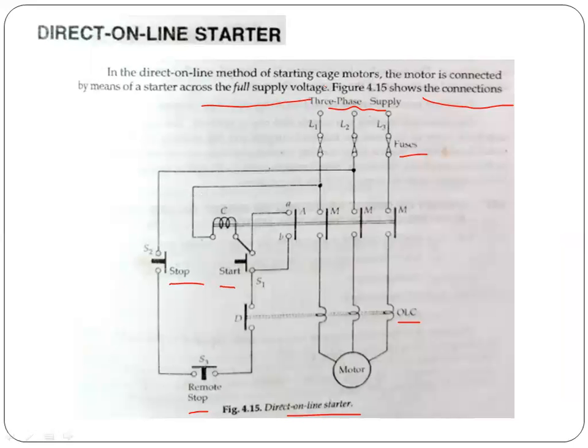So, see, this is the C point. This is the contactor C. Now this contactor is connected with the lines of the supply. When this start push button is pushed, then this contact gets closed and this coil gets energized. This will attract this auxiliary switch and these main contacts, and this path will be closed and the motor will get supply and switch on. Now if we press the stop button, then these points get disconnected, this coil loses its energy and these contacts will open and the motor will stop. That is the main function. Now, under voltage protection.